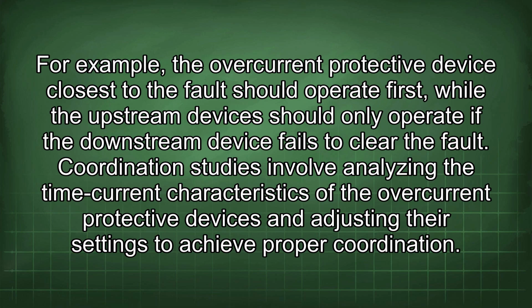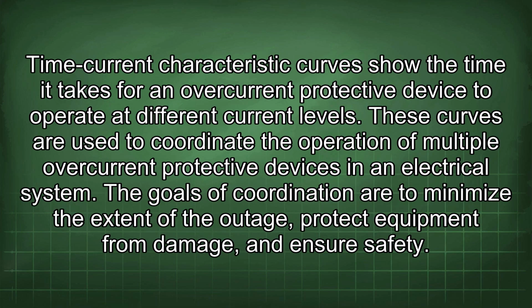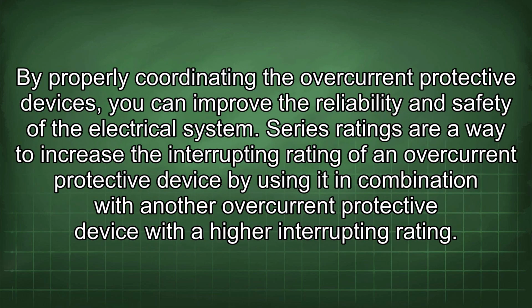Coordination studies involve analyzing the time current characteristics of the overcurrent protective devices and adjusting their settings to achieve proper coordination. Time current characteristic curves show the time it takes for an overcurrent protective device to operate at different current levels. These curves are used to coordinate the operation of multiple overcurrent protective devices in an electrical system. The goals of coordination are to minimize the extent of the outage, protect equipment from damage, and ensure safety. By properly coordinating the overcurrent protective devices, you can improve the reliability and safety of the electrical system.